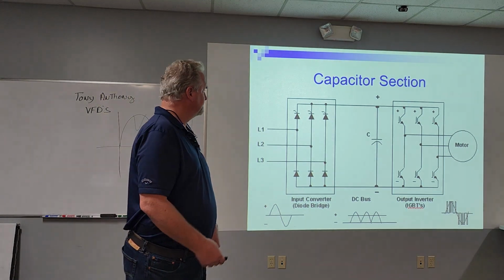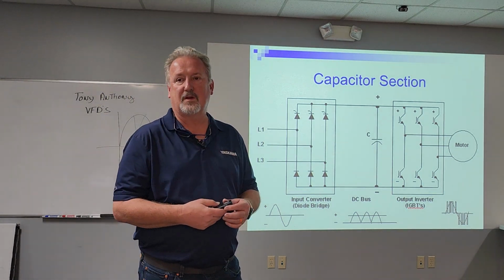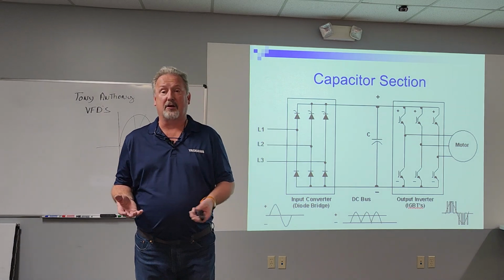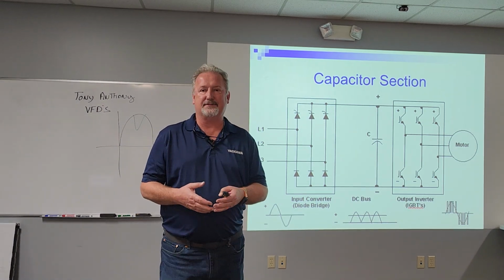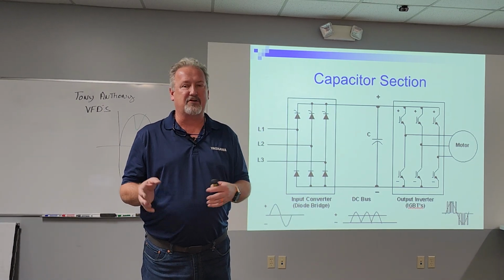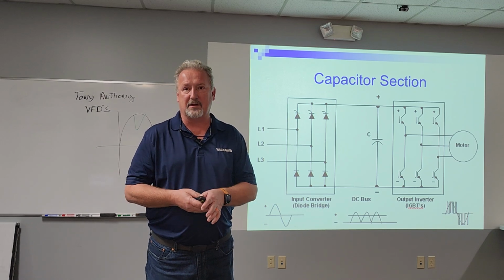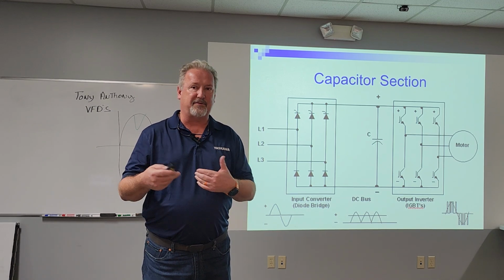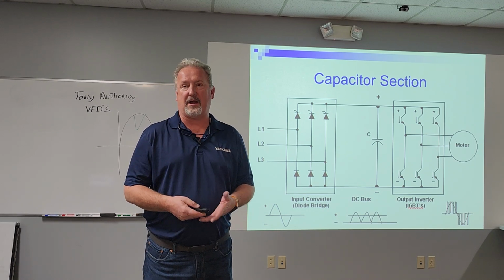Okay. How hard is it to change capacitors on a drive like this? It depends. Smaller drives, most of them under 20 horsepower, we say it's not even worth it. On larger drives, when you start getting above 40, 50 horsepower, it depends on the brand.